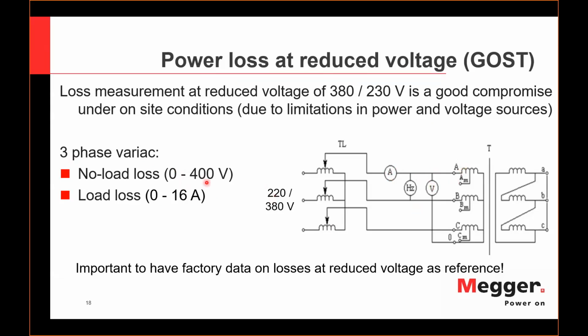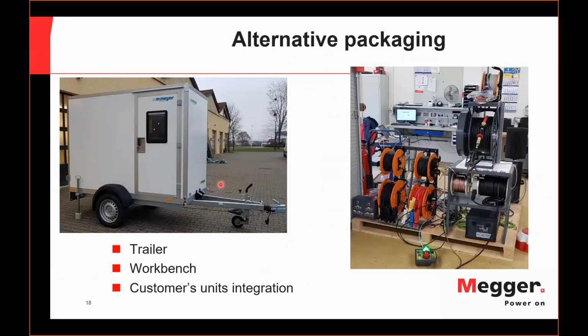It's important not to confuse it with a factory test, because in this test van we are talking about a compromise solution, a solution that only gives you 400 volts, which is maybe fine to test the distribution transformers that have the winding rated to 400 volts. In that case, you are close to rated conditions, but it's not okay to test transmission transformers. Basically, it's not okay to try to compare it to the factory settings. But if you happen to have a manufacturer reference performed at reduced voltages, then it's a direct comparison. When the transformer was new in the factory, tested with 400 volts, you know what loss has been produced by the core or by the windings, and you can easily compare it to this reference.